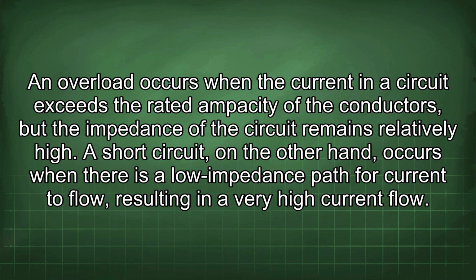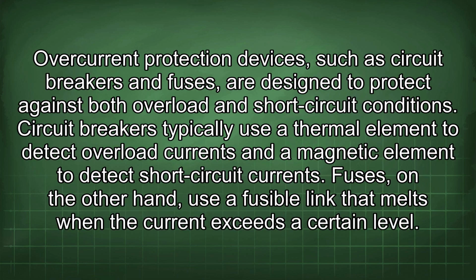A short circuit, on the other hand, occurs when there is a low impedance path for current to flow, resulting in a very high current flow. Overcurrent protection devices, such as circuit breakers and fuses, are designed to protect against both overload and short-circuit conditions. Circuit breakers typically use a thermal element to detect overload currents and a magnetic element to detect short-circuit currents. Fuses, on the other hand, use a fusible link that melts when the current exceeds a certain level.